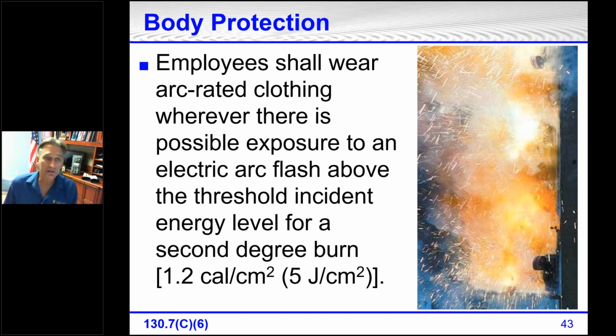Employees have to wear arc-rated clothing whenever there's a possible exposure to an electric arc flash above the threshold incident energy level of a second degree burn, and that's anything above 1.2 calories per square centimeter. Mentioned that number a while ago. That is the arc flash boundary. Anything above that becomes a second degree burn, and then on up to even a third degree burn above that.